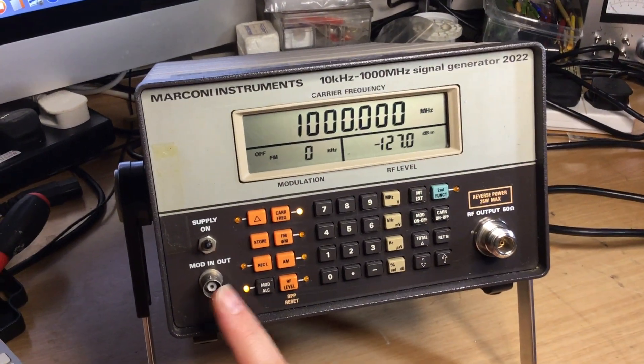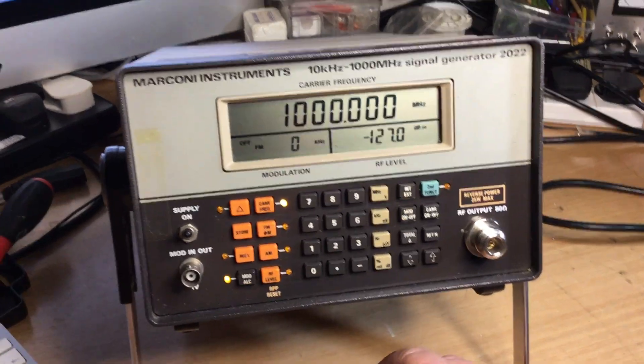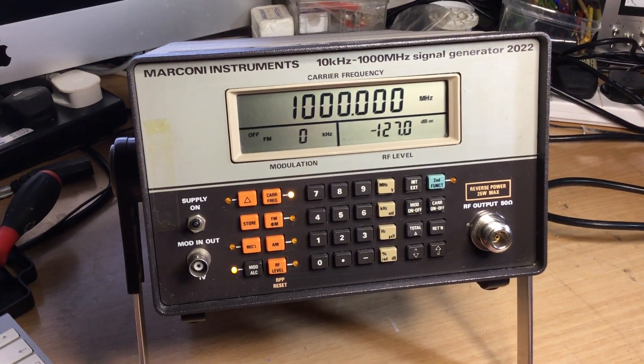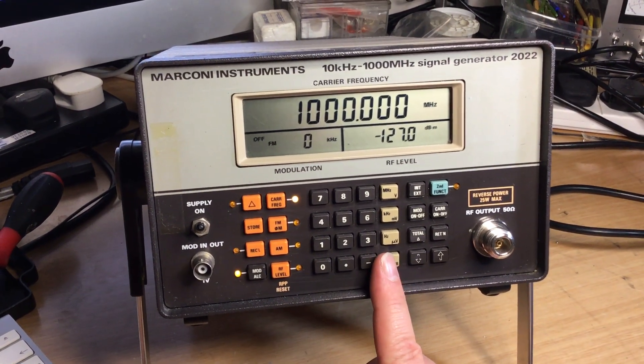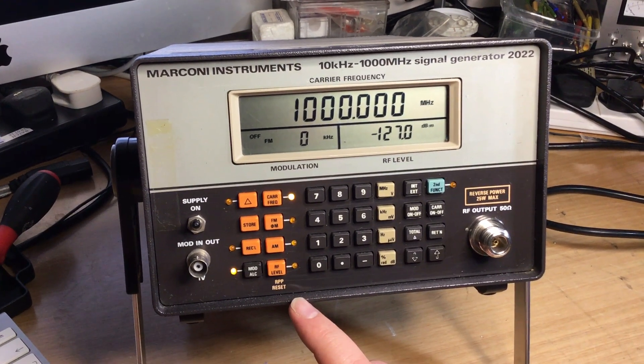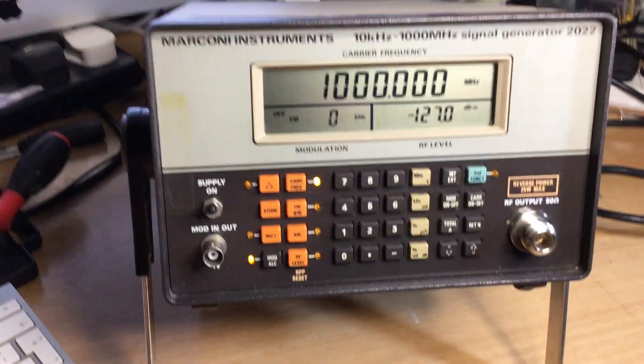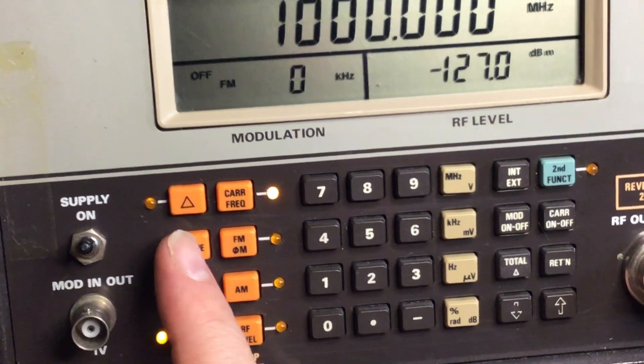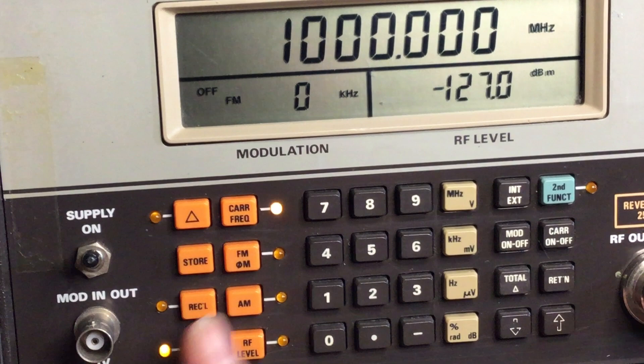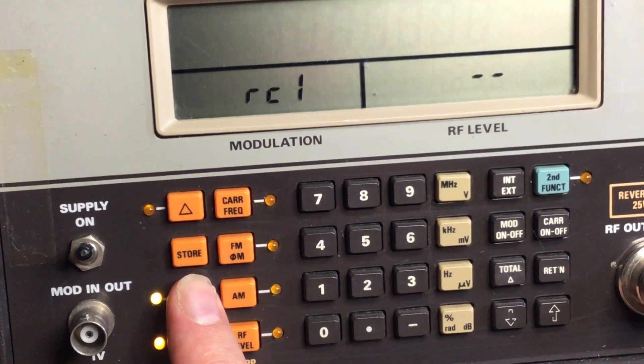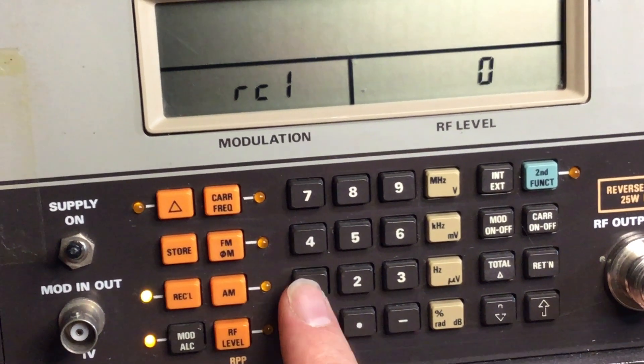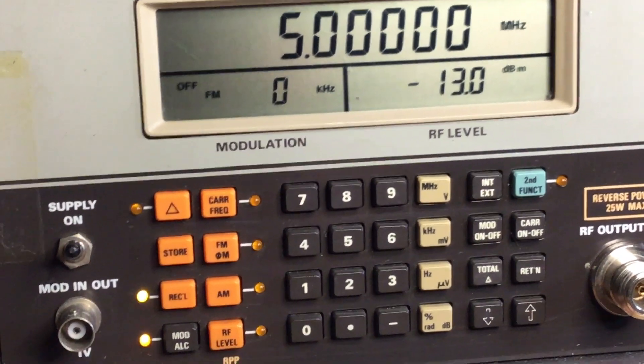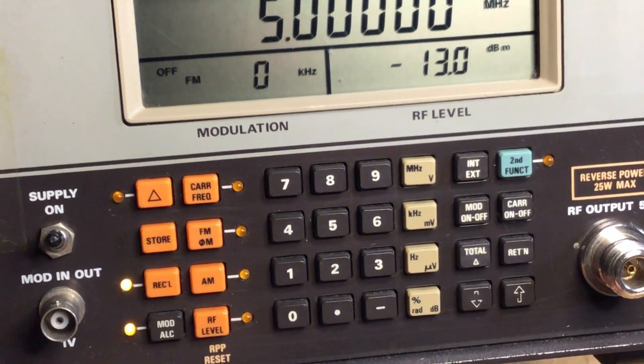They've got an external mod in/out socket there for different modulation standards above and beyond FM, phase mod, and AM, which is what this signal generator does. We've got recall and store on the front here, so you can use the internal memories as well. So I could recall, for example, a setting from memory, and I could even store as well if I wish to.